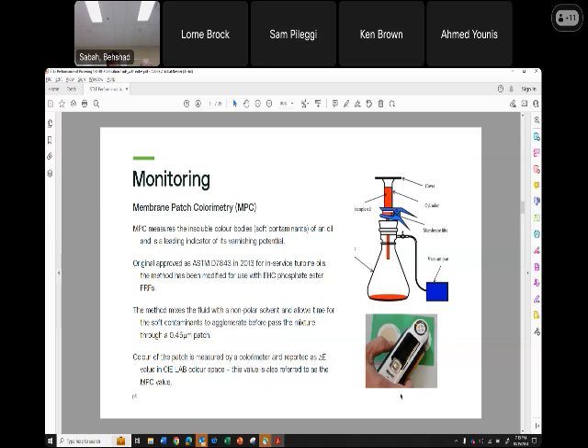We basically take a fluid sample, I believe it's 50 milliliters. We pass it through a 0.45 micron screen and we capture soft body contaminants on the filter membrane. And this is on top of, what's it called, the settling time. There's stuff like 48 or 72 hours settling time where the sample is just left to rest before being tested in this apparatus.